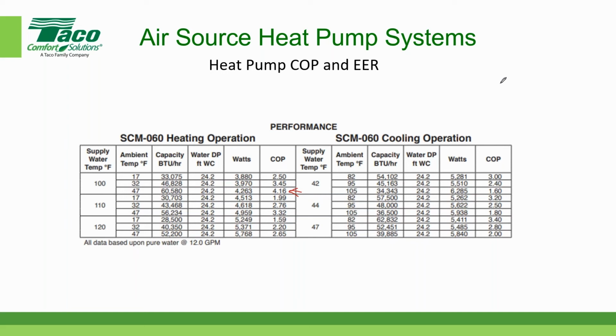Right, and manufacturers, for the same set of conditions, they'll get higher COPs because they use much more efficient compressors, much greater heat transfer surface area in their heat exchangers. And so by changing, let's not change the refrigerant for a moment, by just changing the operational characteristics and the efficiency of the compressor, and by changing the amount of surface area, some manufacturers can get their COPs up to as high as 5, and I've seen some that are around 6. So these systems can be very, very efficient.